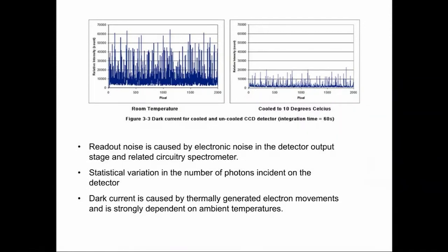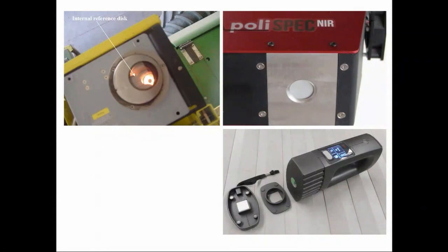Now, to compensate for that, instruments include something called referencing. You can imagine as your temperature varies, you may be generating more current in the diode based on temperature over time. If the temperature rises or lowers, that could influence what you are perceiving as light rather than as light reflected from the sample. So let's say you measure a sample and it's cold outside, you'll get one reading, and if it's warmer, you'll get a change. The sample temperature matters too, but here we're talking about the instrument temperature changing.